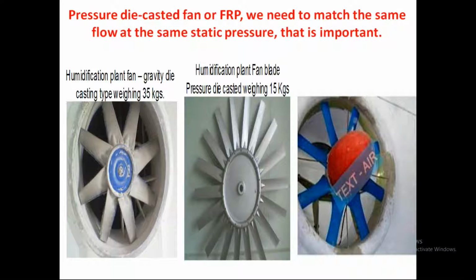Coming to the impeller, what I have been talking about before is the centrifugal impellers. This is an axial flow fan impeller. Many of the textile mills are implementing this. The previous impeller was a gravity die cast fan blade, which was almost 35 to 40 kgs. This impeller is 1200 mm dia. Instead of 8 leaf, this is replaced with 18 leaf.